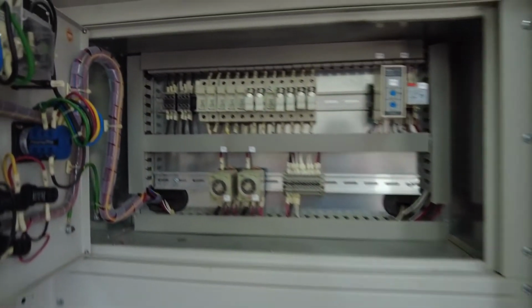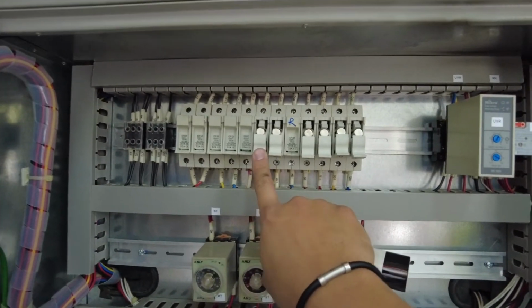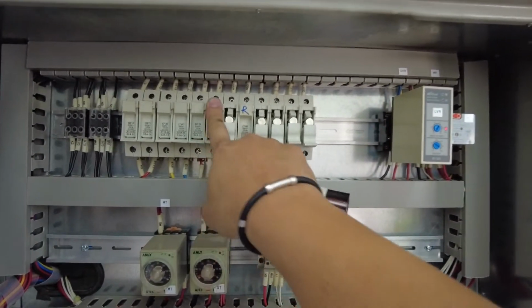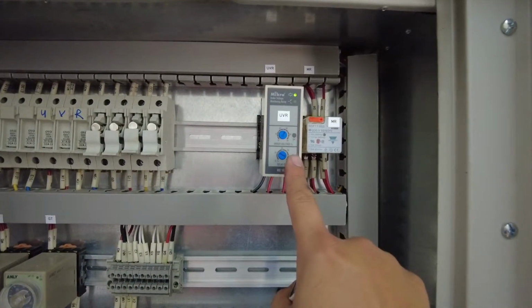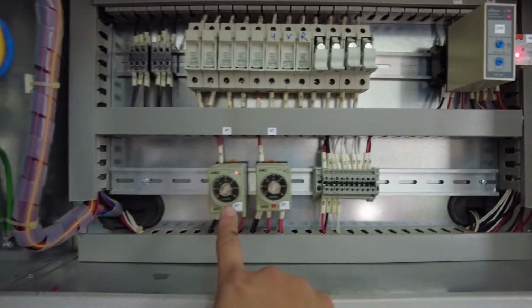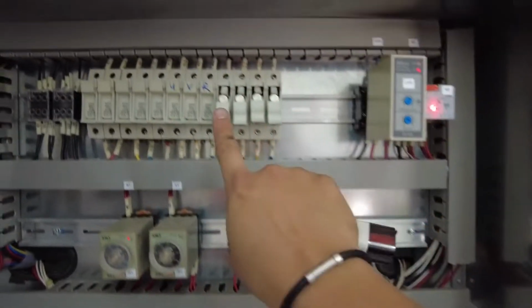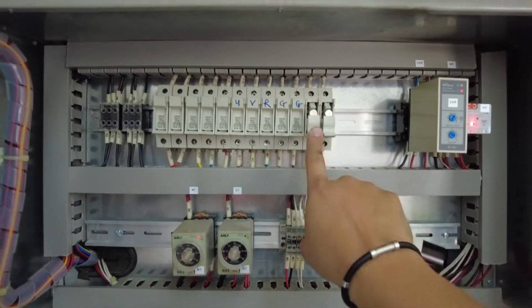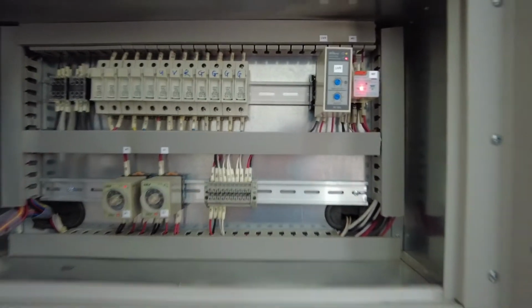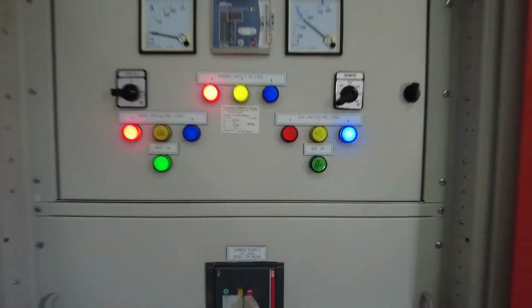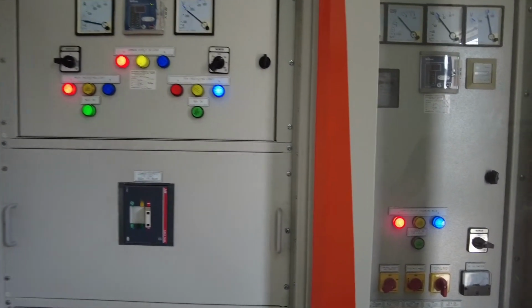Okay. So now we want it to stop automatically. First of all, we put back this fuse to allow the UVR relay to activate first. Okay, UVR relay activated. Allow the timer to steady down. Okay, then only we put back the genset fuse. Okay, now after 3 minutes, the genset will stop automatically. So this way I can confirm the genset can run automatically during DNB power interruption. Alright, everything auto. Okay, now we just check the cap bank.